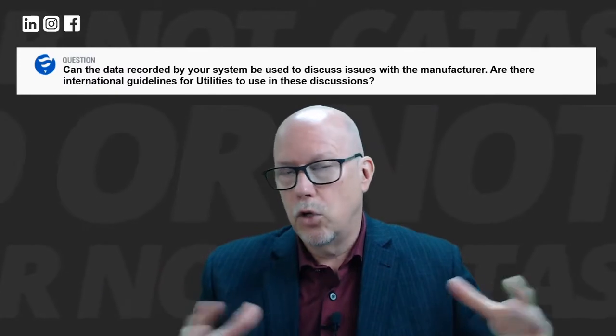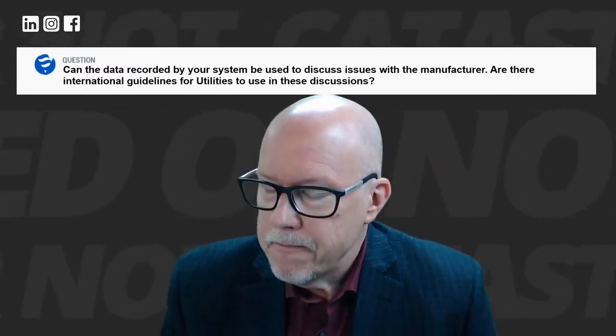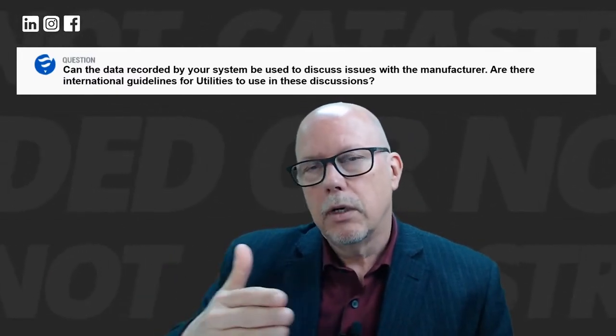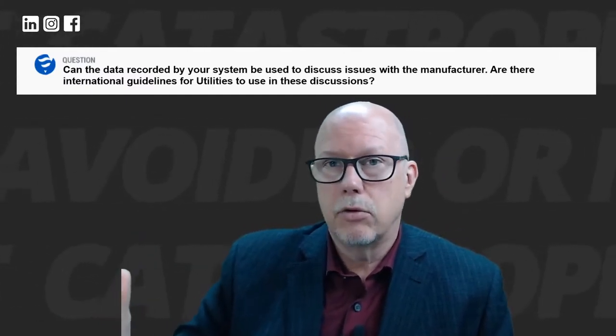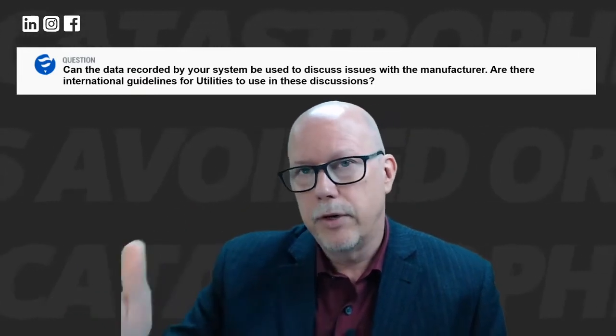So their tolerances are used, but we use our own. They're similar, but ours are mostly for results dynamically, whereas CEATI's tolerances, if I remember correctly, are based on the assembly floor, unit cold, not moving. And we have four criteria, which corresponds to the ISO philosophy, where you always have four severity levels.